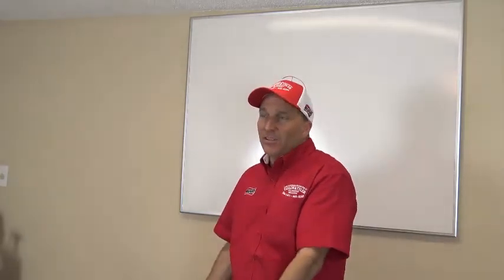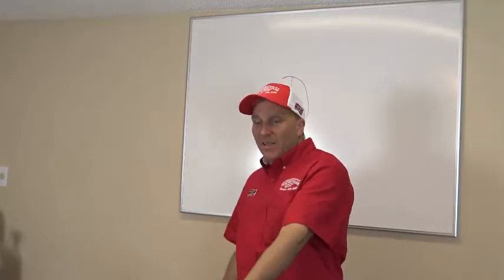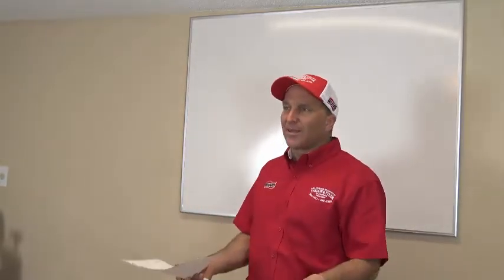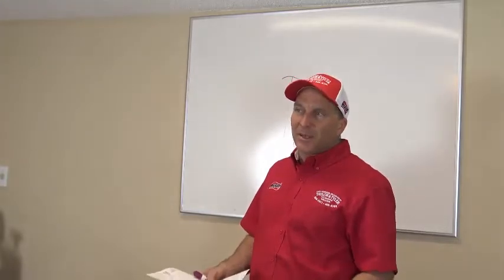You're looking at about $350 to do that, but you really need to do this because you're killing the efficiency of your system. Your dog is laying at the condenser, he's kicking all the dirt up inside of it. There's a 1 foot pile of ants inside of your condenser here, and I cleaned it all out, but I'm telling you, next week it's going to be back the same because your dog's kicking all the dirt back into it. He's laying right next to it. Why can't you give them a price to raise that condenser? Isn't that what needs to be done to fix the problem?